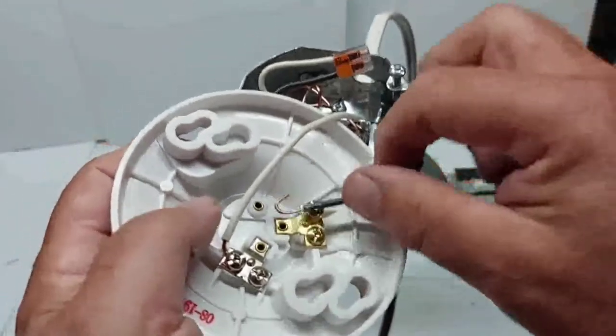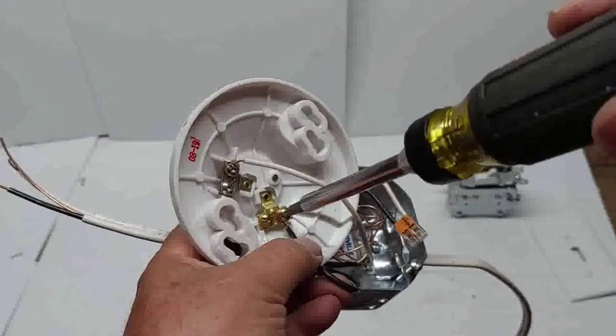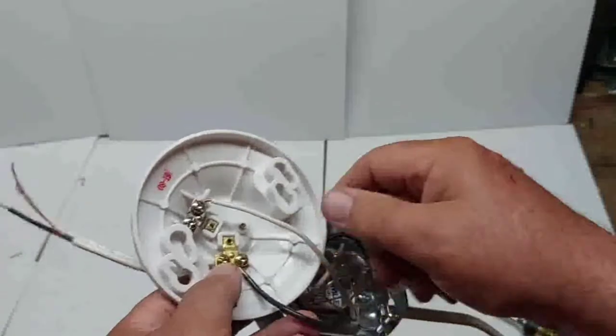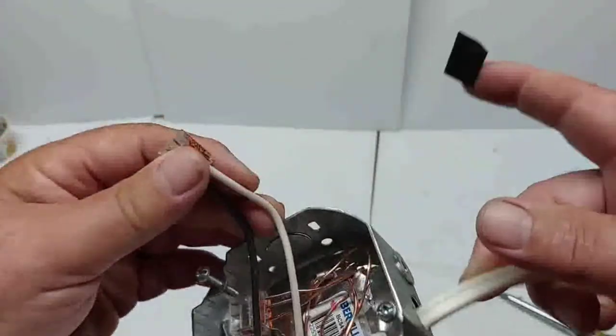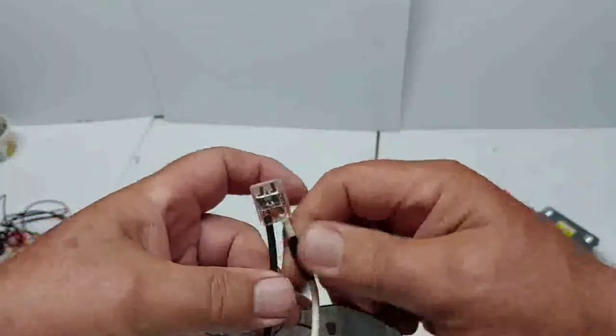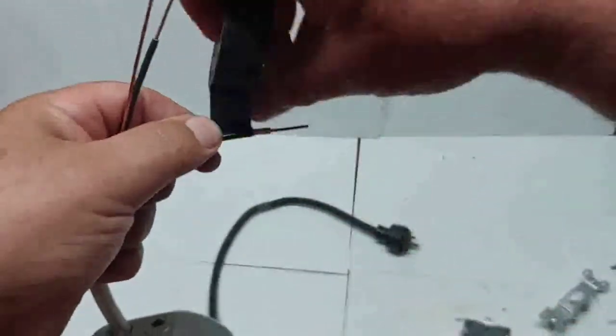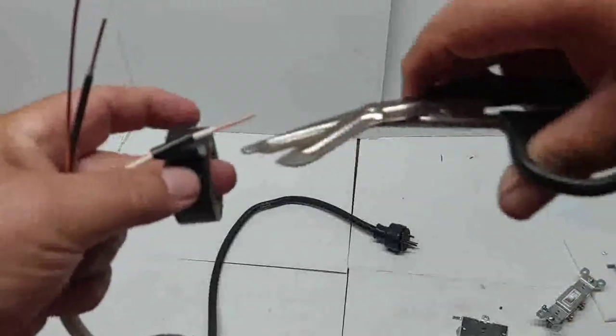The black wire coming from the switch goes on the gold terminal at the light. So you've got a white coming from the power going to the silver, and the black coming from the switch going to the gold. Now connect the power coming in to the neutral wire to give power to the switch — using a Wago connector. Put a black piece of tape on the neutral wire to remind everyone that this is the hot wire going to the switch, not a neutral.